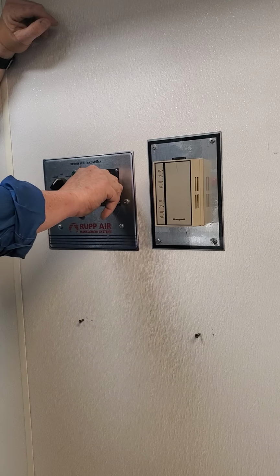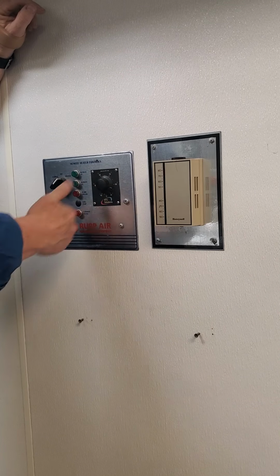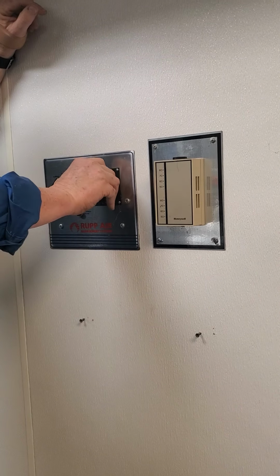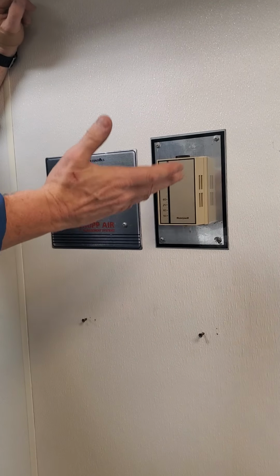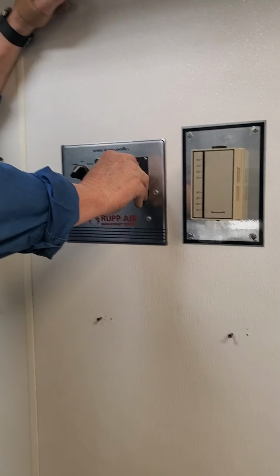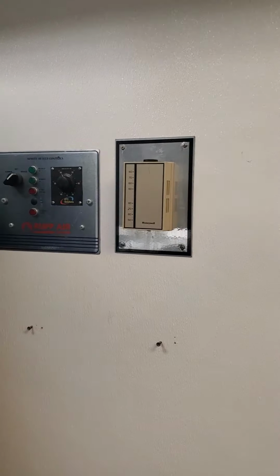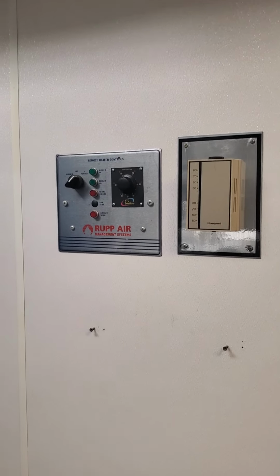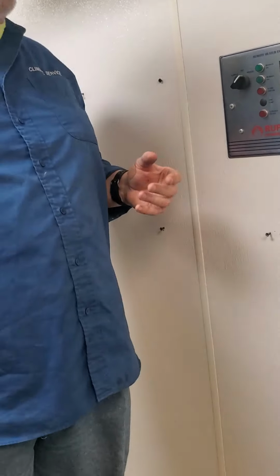If it's a makeup air unit, I'd come in here and they'd have it set at like 90. It's like, dude, it's zero outside, it's never gonna get there, it's just gonna run at high fire all day. So I just keep them at like 55 or 60 - you're just tempering the outside air, you're not trying to heat it. They thought it was supposed to be hot. It's not gonna be hot.